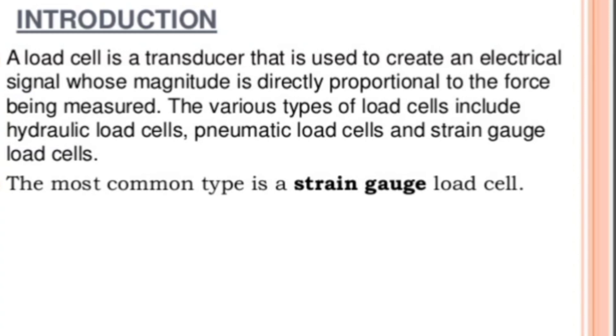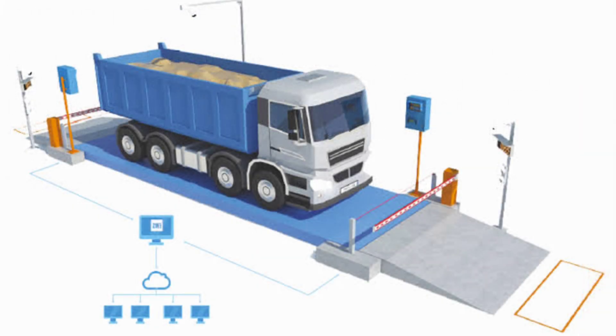What is a load cell? A load cell is a transducer that uses strain gauge principle to create an electrical signal whose magnitude is directly proportional to the force being measured. Whenever a vehicle comes to a load cell or weighing balance, the load cell produces electrical signals using strain gauges. When you apply the force, the resistance will change, and based on resistance changes, the voltage will also change.